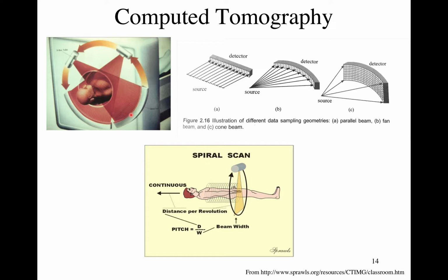And so at that point you say, well, let's just rotate it faster. So they kept rotating it faster and faster until finally the thing's really spinning fast, and you're getting pictures very quickly. Granted, you have to make more X-rays per unit time for that to occur, because you run out of X-rays if you go faster and faster. So you need a more powerful tube. Then as that thing rotates faster, you push the patient through faster, and you get the whole data set in seconds, whereas it used to take minutes.